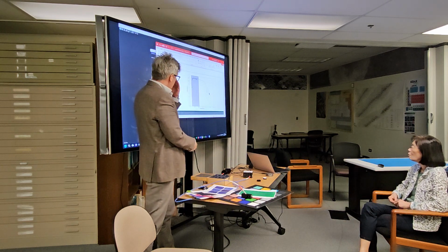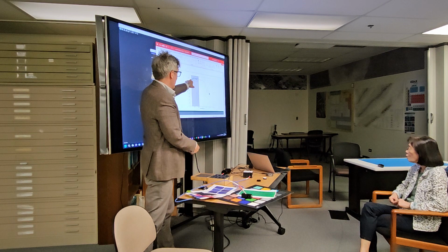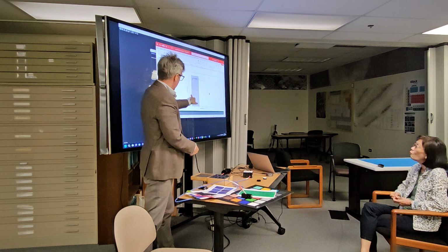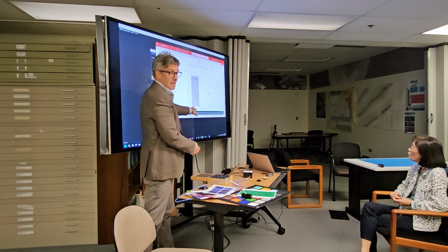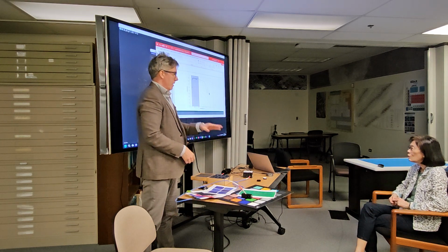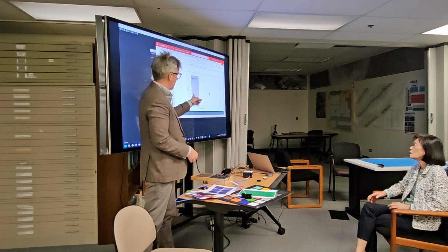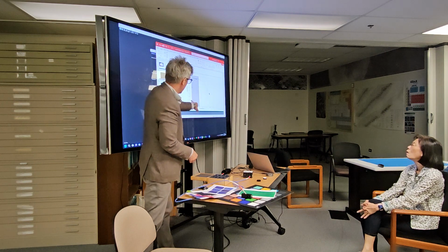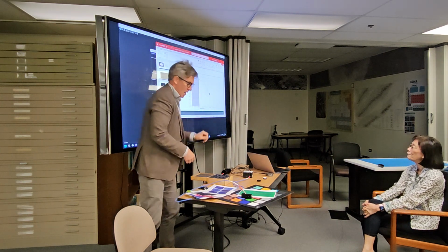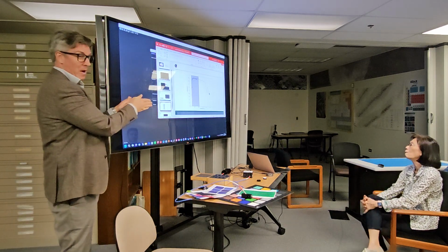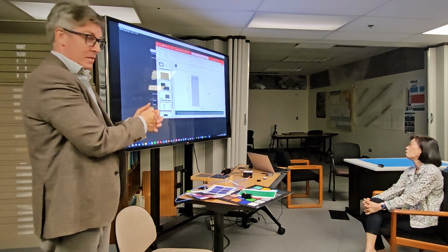So it's pretty high and flat, right? It's between 90% and 100%, so it reflects 99% of the light that falls on it. And this is kind of flat. Not so good down in the extreme shortwave visible blue. So that's very good at reflecting light, it reflects it equally, and it's very well characterized. You'll notice it isn't as good at longer wavelengths, but that's okay, because this spectrometer is only looking in this part of the spectrum. The key point is that it reflects nearly all of the light that falls on it over the wavelength interval that we care about, which in this case is 200 to 1100 nanometers.